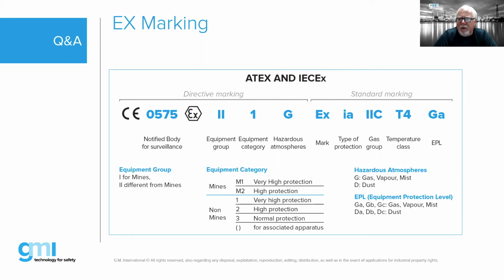And then your EPL, which is your IECEx marking, which is now adopted under the ATEX directive, GA, which is basically telling us that our explosion protection level is for a gas atmosphere with an A. So it's either going to be... Why don't you elaborate a little bit on that T4? Because I remember one of the latest registrants posed a question about T6, what that temperature means.